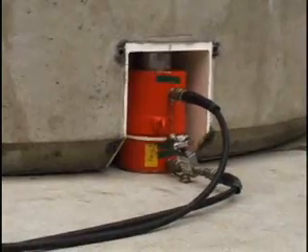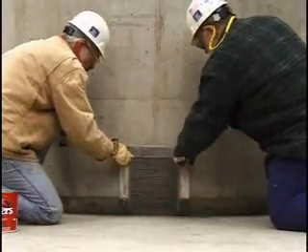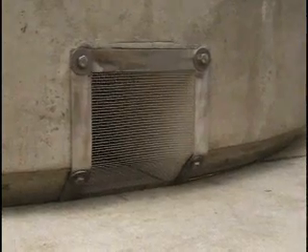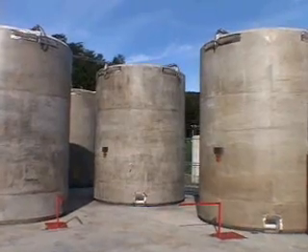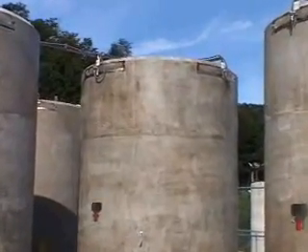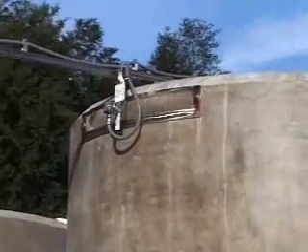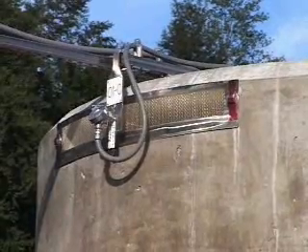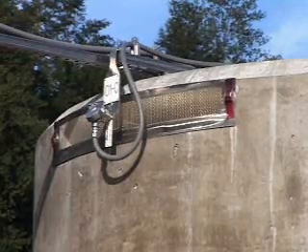The vents that allow air in to cool the outside surface of the sealed fuel canister are covered with screens to keep out leaves and small animals. The air that enters these vents exits through a screen vent at the top of the storage cask, where the temperature is continually monitored. Although routine radiation readings on and around the casks will be taken, air temperature monitoring can provide preliminary information in the event of a change in the integrity of a fuel canister.